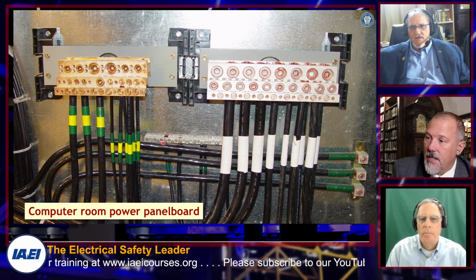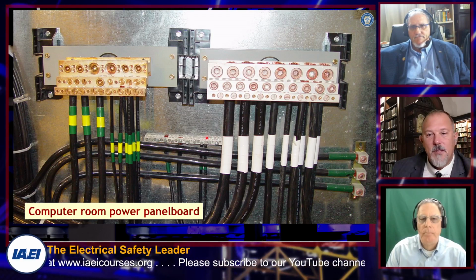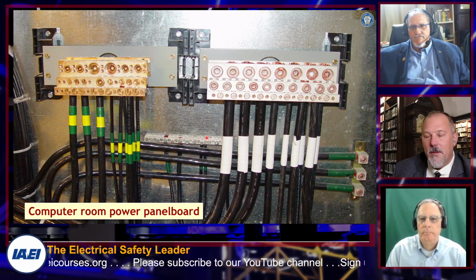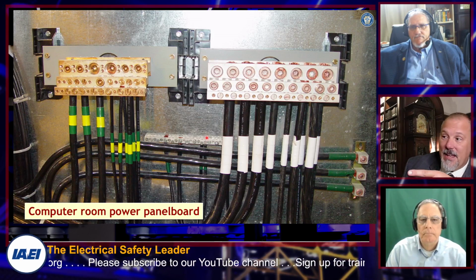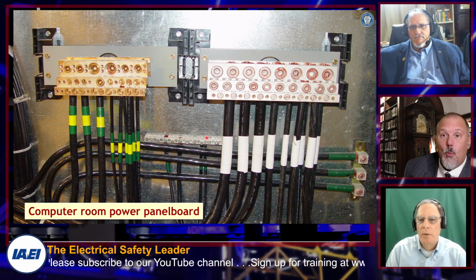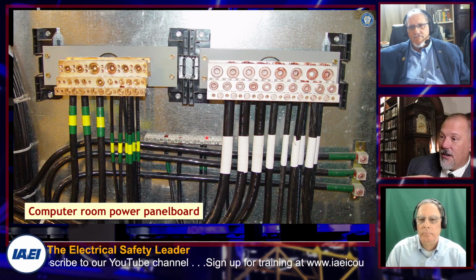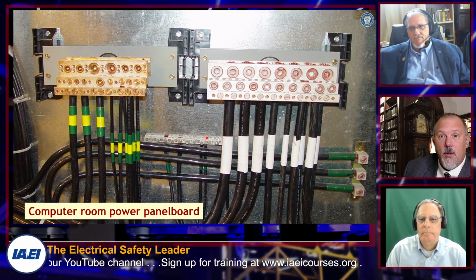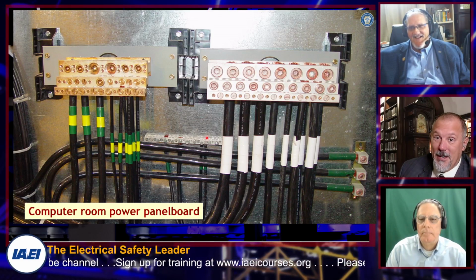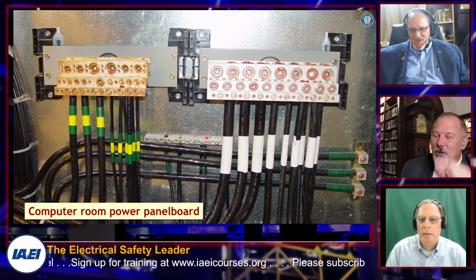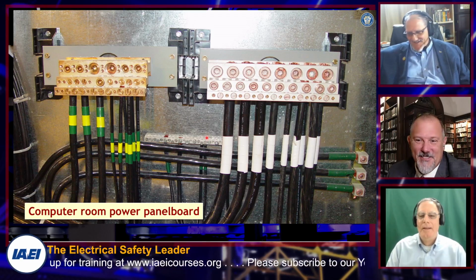So, and this one here as well - just based upon where it's located, if you saw a conductor wrapped in white, located on a lug that's directly connected to the equipment, and it's not service equipment, you've got an issue.